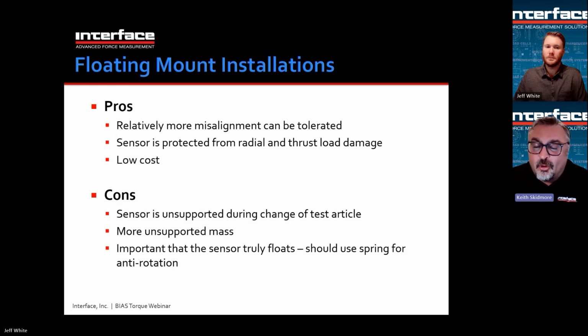Cons: the sensor's unsupported. So say you have a system where you're going to test motor after motor after motor. Every time you disconnect the test article motor, the whole sensor can flop over. So it's not supported. That can actually damage the coupling that's on the other end of it. So if you're going to break the drive line a lot, a supported foot mount sensor might make more sense. Again, there is more unsupported mass for high RPM use. It may be better to have a pedestal mount where you have two shorter spinning sections with couplings, versus the entire assembly of the torque sensor housing as mass supported in the rotating section.